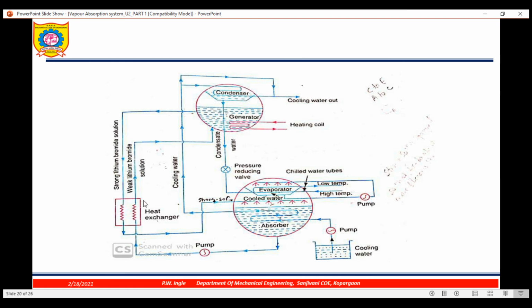And this heat exchanger, what does it do? It will take heat from the strong solution, strong lithium bromide solution, which is coming from the generator, and give it to this weak lithium bromide solution. Weak means it consists of water refrigerant. Okay, and this completes the cycle. So where are we getting the refrigerating effect? Here we are getting the refrigerating effect. So this completes the lithium bromide vapor absorption system. So thank you.